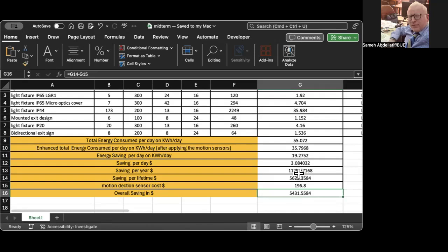Another point is that we ignore the electricity consumption of the sensors, and this is again a very basic and sensible assumption because simply sensors are like current loads with a very low current consumption, usually in the milliampere range. We are considering 100 to 200 milliamperes. So usually we can easily ignore the impact of their power consumption with respect to the system. So this is again a valid assumption, but of course you can make it in a more accurate manner, and you can calculate the typical power consumption of the sensors, and you can add it to the system as an added load. So instead of just making this 35% reduction, it will also include an addition of the sensor power.